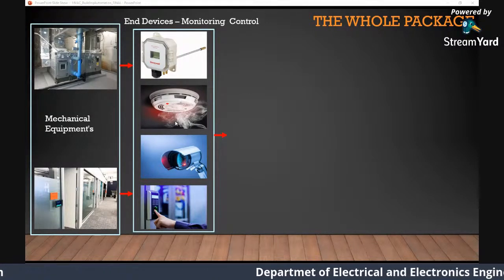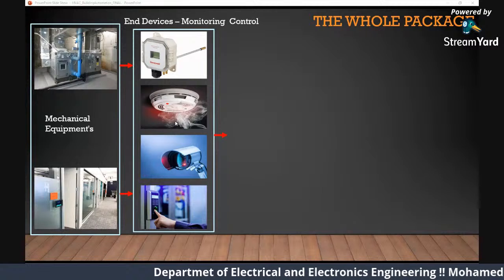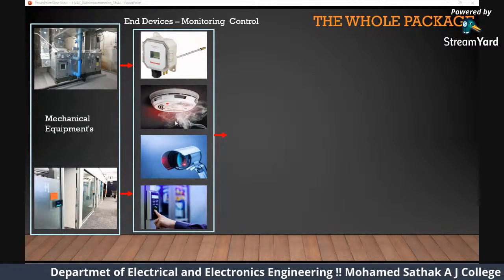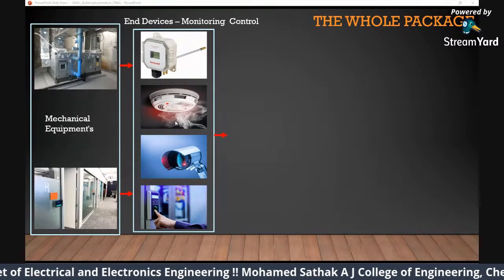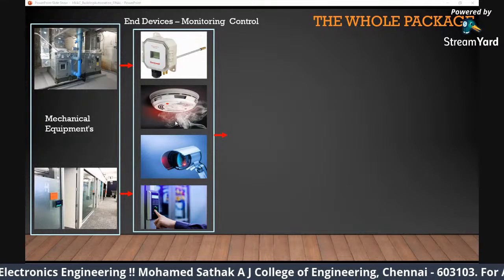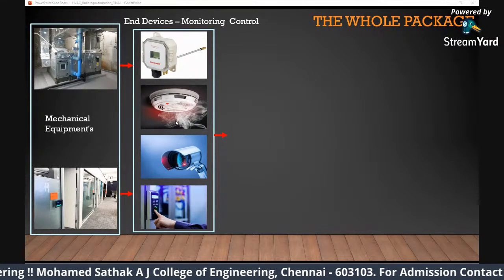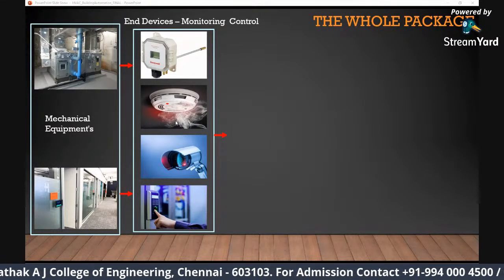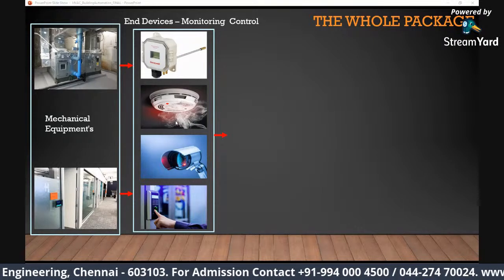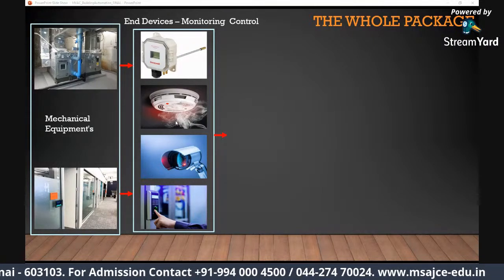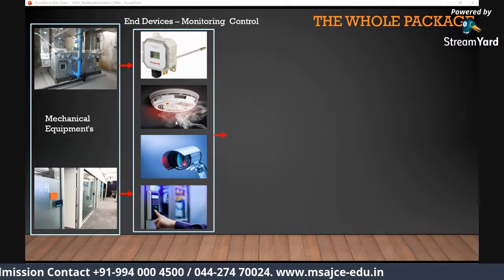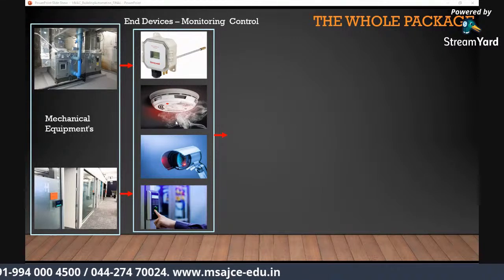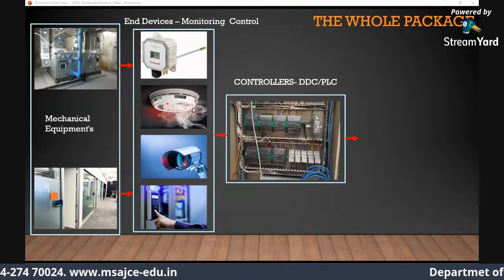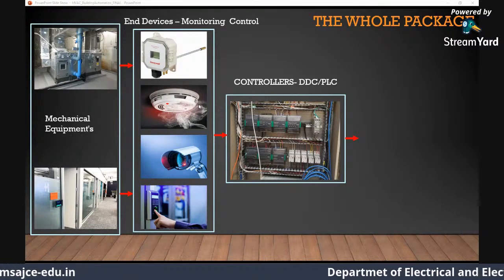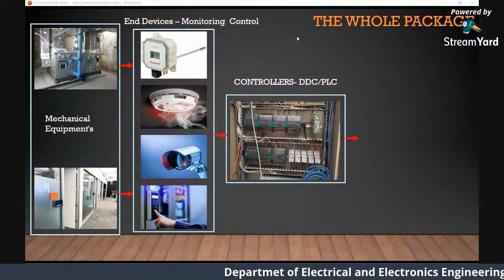So all this will be mounted inside. All your temperature sensors, pressure sensors will be mounted inside the AHU. Honeywell will mount it. All your security cameras, all your biometrics, everything will be mounted by Honeywell. Honeywell, or Siemens, Schneider, will not manufacture or deal with mechanical equipment. We deal with only electronic end devices. So we mount all this on your mechanical devices. Okay. Now we have our controllers. All these end devices for monitoring and control will be wired to your controllers as inputs.